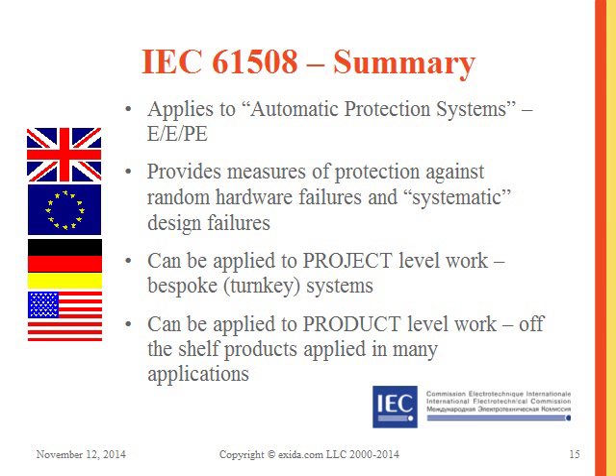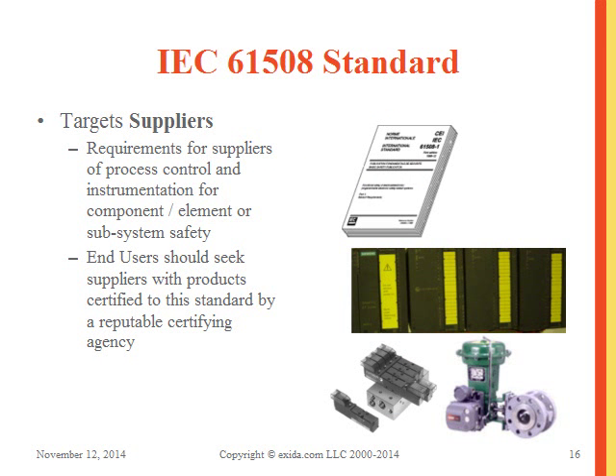IEC 61508 applies to automatic protective systems — EEPE systems. It provides measures of protection against random hardware failures and systematic design failures, and can be applied to project-level work such as a turnkey system and product-level work such as off-the-shelf applications. IEC 61508 targets suppliers and their requirements for process control instrumentation at the component, element, or subsystem safety level.